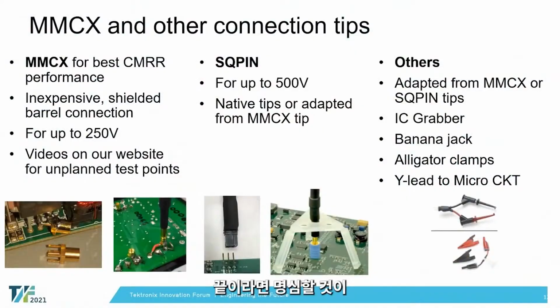So speaking of tips, just a couple of other things to keep in mind. We offer a variety of different tips for IsoVu. The main one that you'll see used most often, which has arguably the best performance common mode rejection wise, is our MMCX style tip. MMCX is a shielded barrel style connection. It's relatively inexpensive. You can get surface mount connections on DigiKey and other vendors for less than $2. And it's for voltages just under 250 volts or so. So, obviously, these are for planned test points in most cases.